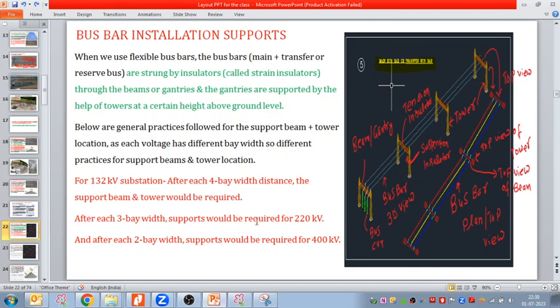If we have 220 kV, then after each 3 bay width supports would be required. And if we have 400 kV, then after each 2 bay width, because in 400 kV my bay width is increased. For example, for 132 kV my bay width is 12 meters, so after 4 bays, that means after 48 meters. For 220 kV my bay width is 16 meters, so after 3 bays, that means again after 48 meters, we are planning the next support. In case of 400 kV my bay width is 24 meters, so after 2 bays, again 48 meters. So again after 48 meters we are planning the location of the next gantry and tower.